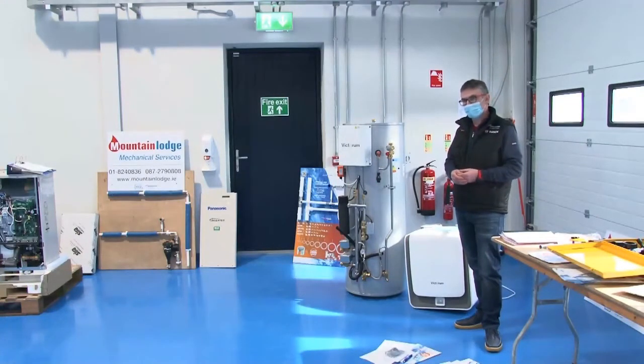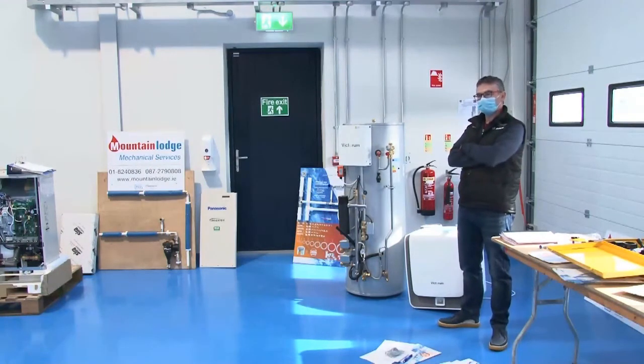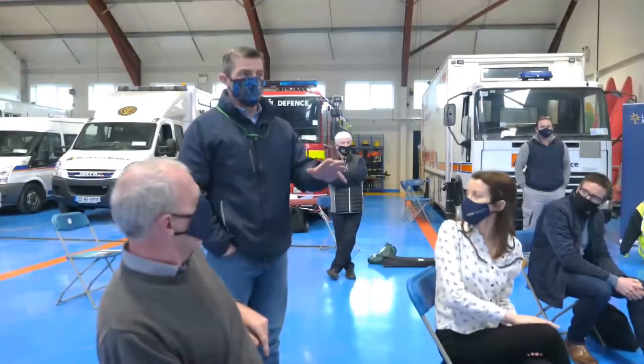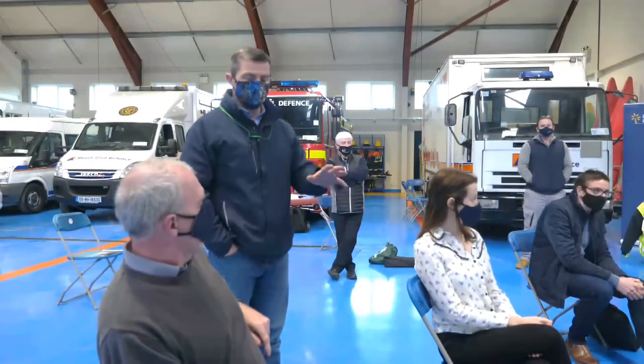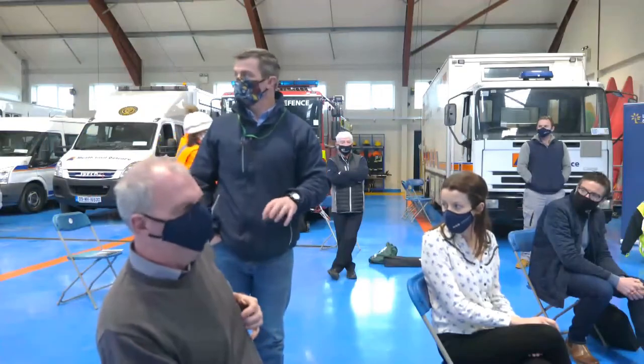Just come back to your fire product then, John. If the manufacturer did send them in, the whole lot came together, and they're EU stamped or EC stamped, that doesn't necessarily mean compliant with the regulations. You have to check to see if the standard is the same standard that we have in regards to the quality of that. Because these are coming from Europe, they may be able to be sold here, but we may not be able to use them.